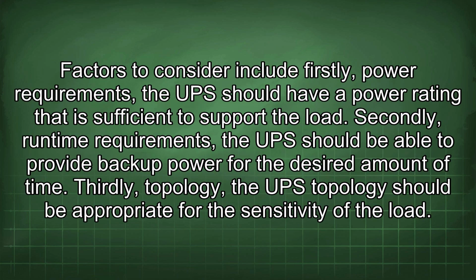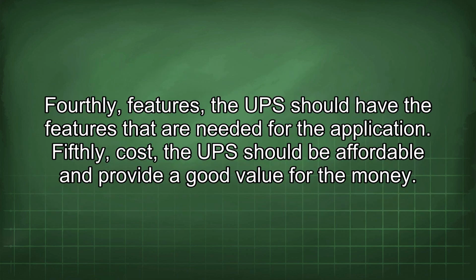Factors to consider include, firstly, power requirements. The UPS should have a power rating that is sufficient to support the load. Secondly, runtime requirements. The UPS should be able to provide backup power for the desired amount of time. Thirdly, topology. The UPS topology should be appropriate for the sensitivity of the load. Fourthly, features. The UPS should have the features that are needed for the application. Fifthly, cost. The UPS should be affordable and provide a good value for the money.